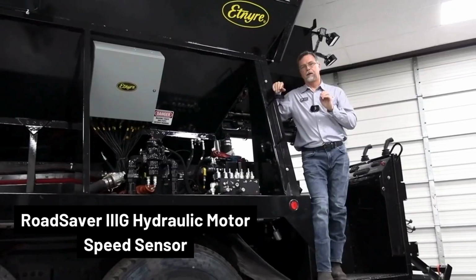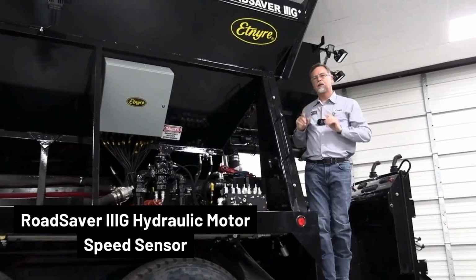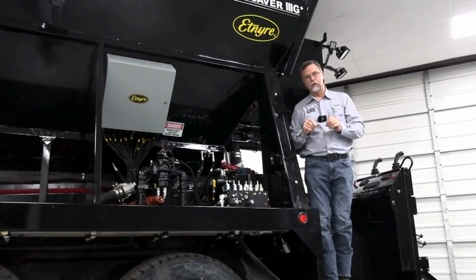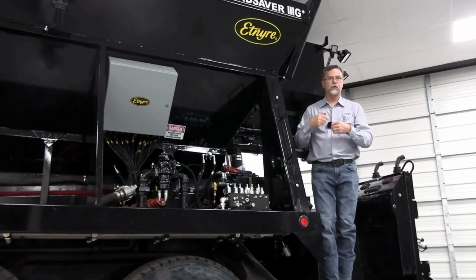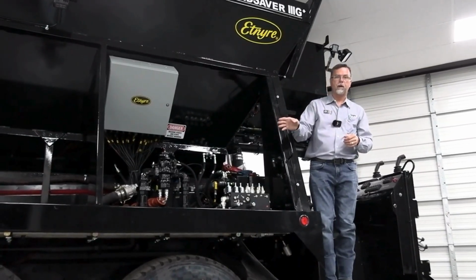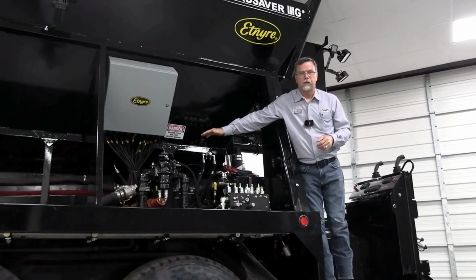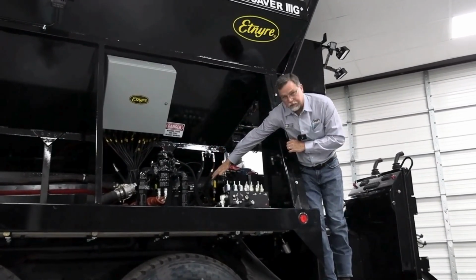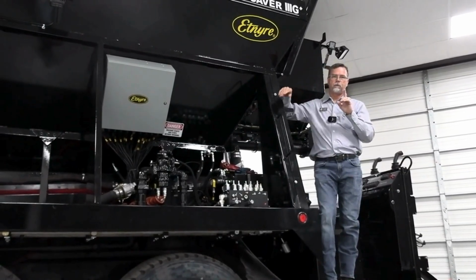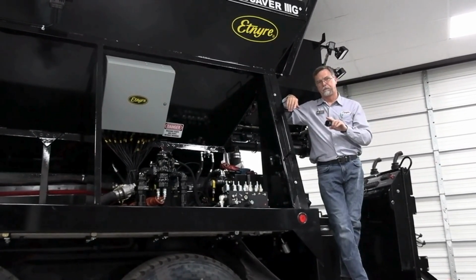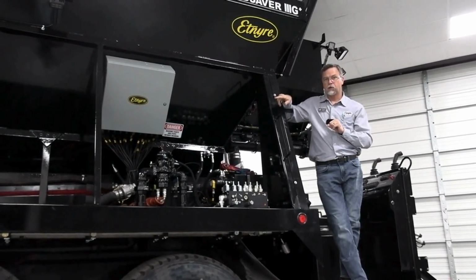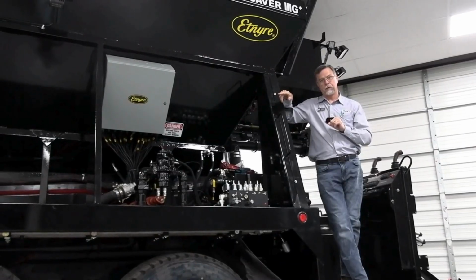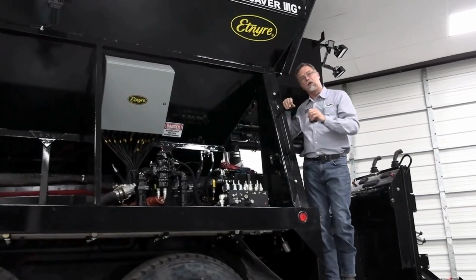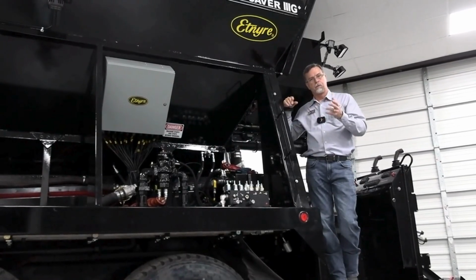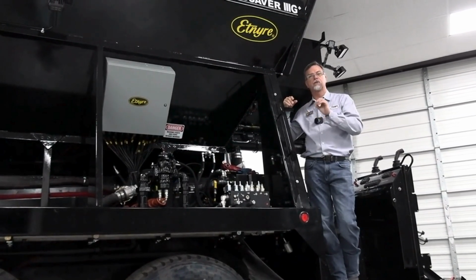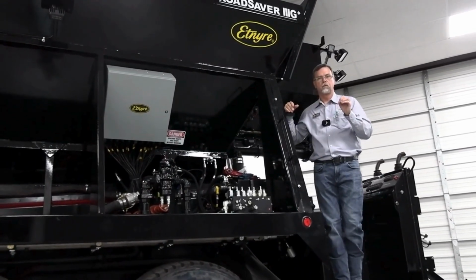The conveyor drive system and the emulsion pump are electronically synchronized, so these drive motors need their own speed sensors. On the emulsion pump, the hydraulic motor has a speed sensor for measuring it. This one has the same physical speed sensor, but it's programmed differently. The sensor driving the emulsion pump is for an OMS motor, and this sensor is driving an OMR motor. The pulses these motors put out are different, so the sensors are programmed for those specific motors.